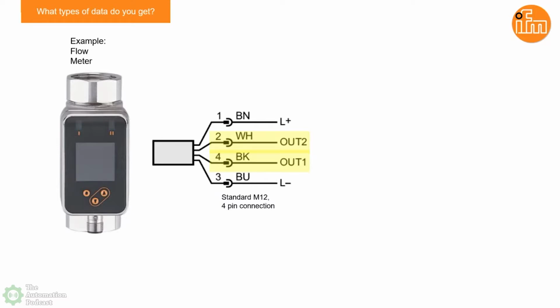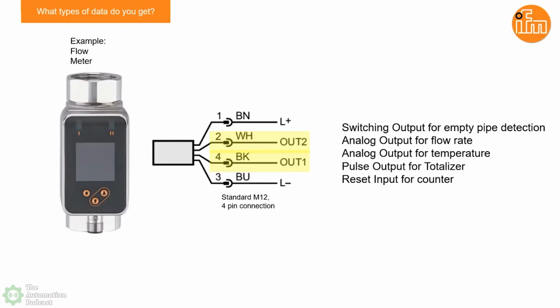For this specific sensor, these two outputs, we have the ability to select what those outputs can be. It can let you know there's an empty pipe in the system. We can take analog outputs here to give you the flow rate, the temperature. We can give a pulse output for a totalizer. We can reset any of the counters here. So a lot of things you can do with the sensor because it's a pretty intelligent device.